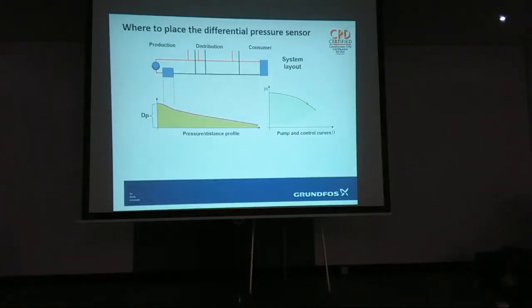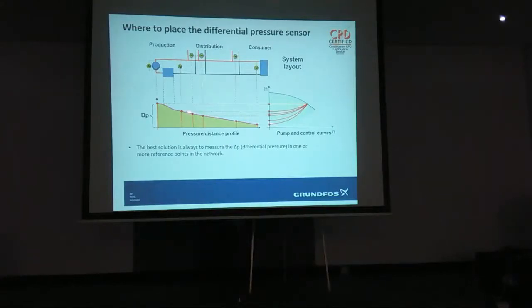And where do you put the sensor? Which is what I just alluded to. The pressure at the pump is still the same. From a selection point of view, if you put it across the pump and maintain constant pressure there, or if you put it out in the system, depending on where it is, you'll get constant pressure there. You'll get the greater reduction in energy because the pressure here will plummet down.